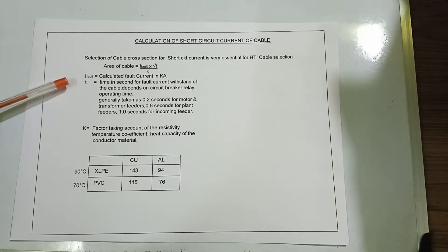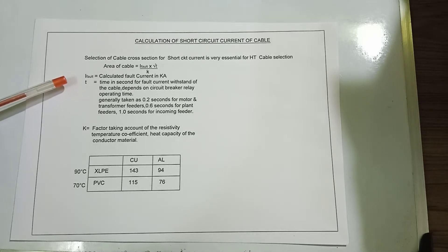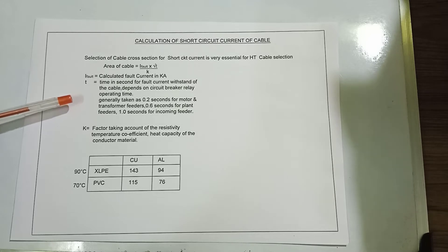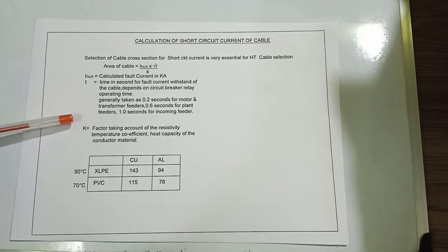t is the time in seconds for fault current withstand of the cable, which depends on the circuit breaker relay operating time. Generally taken as 0.2 seconds for motor and transformer feeders, 0.6 seconds for plant feeders, and 1 second for incoming feeders.